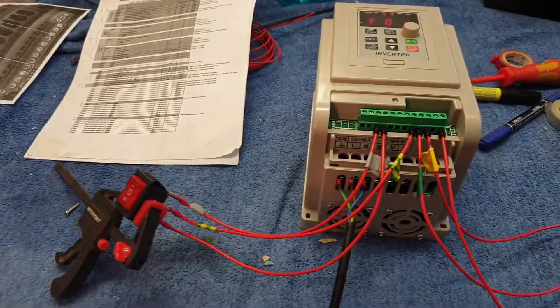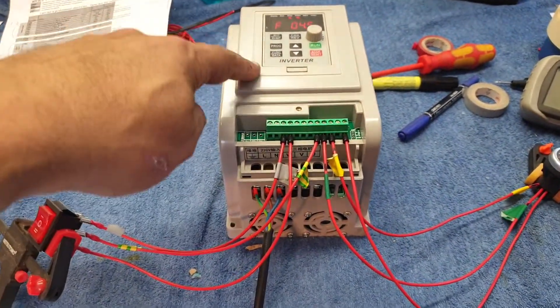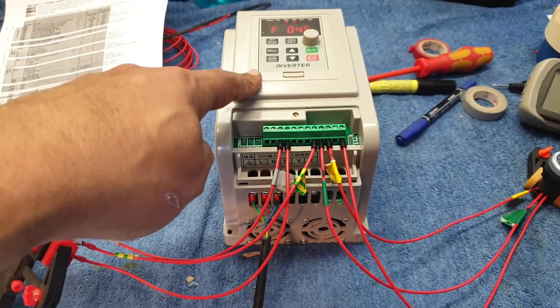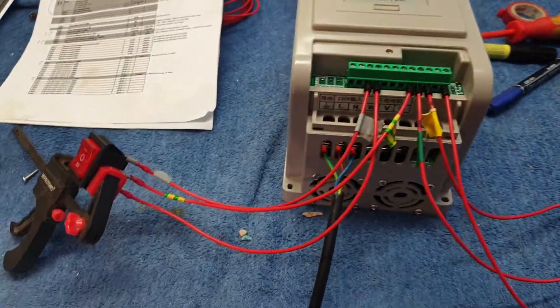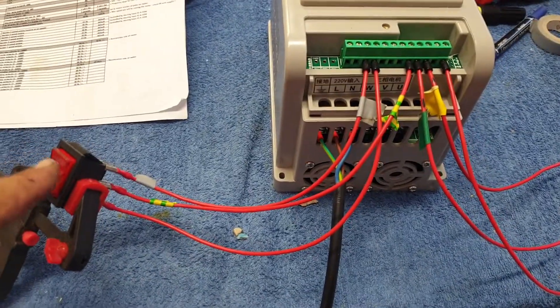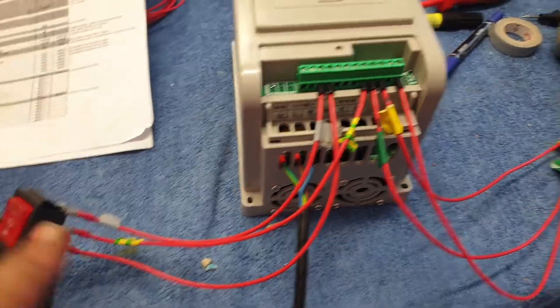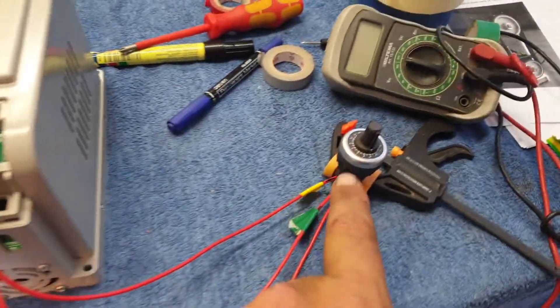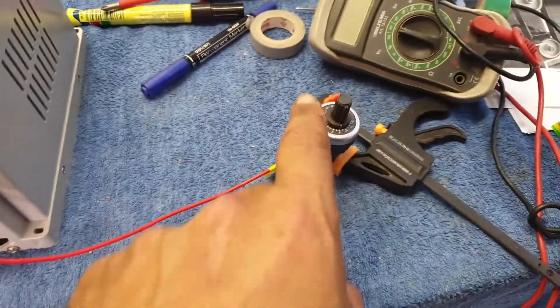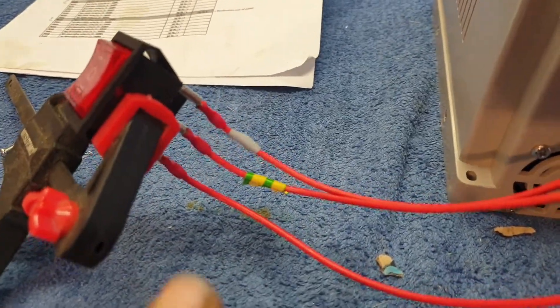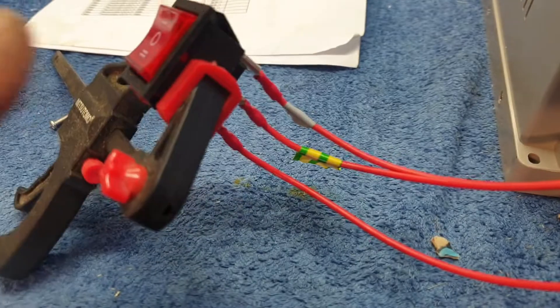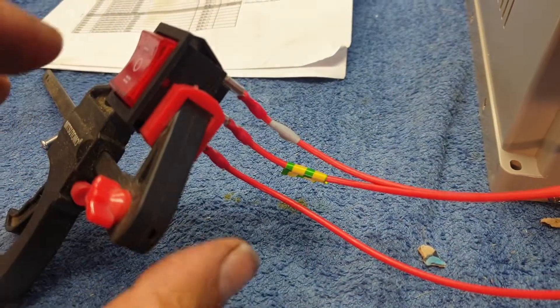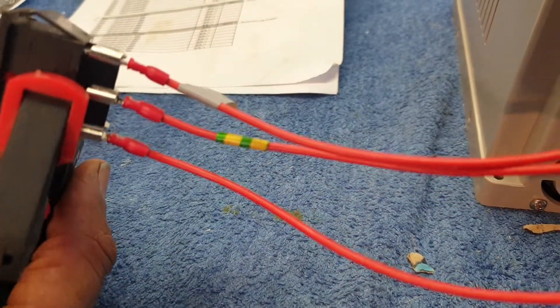This is how to wire the AT1 single-phase to three-phase VFD for power, reverse, forwards, and an external potentiometer. This is a 10k potentiometer. Just to show you, this is a double-pole double-throw switch. You can have a single-pole double-throw since it's all the same, but anyway the middle is the common, two outsides are forward and reverse.